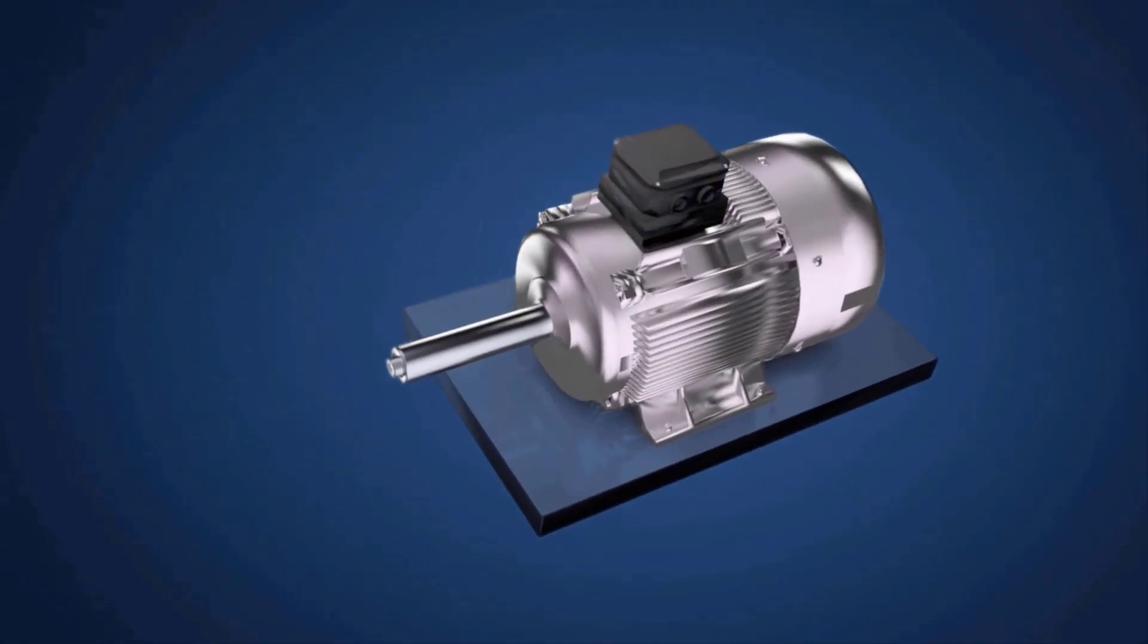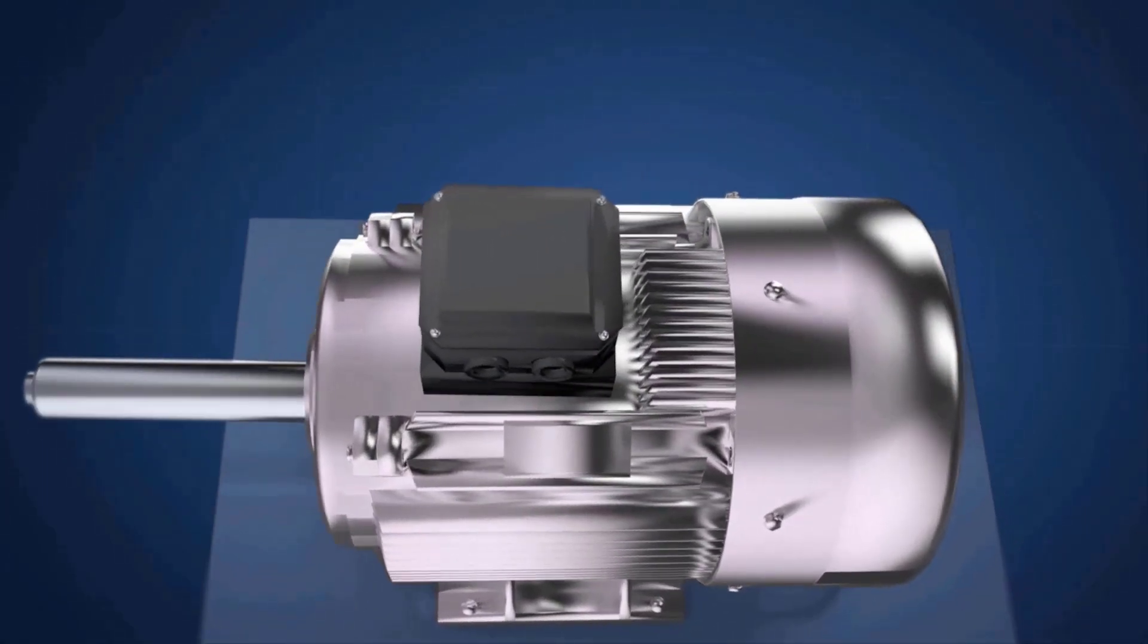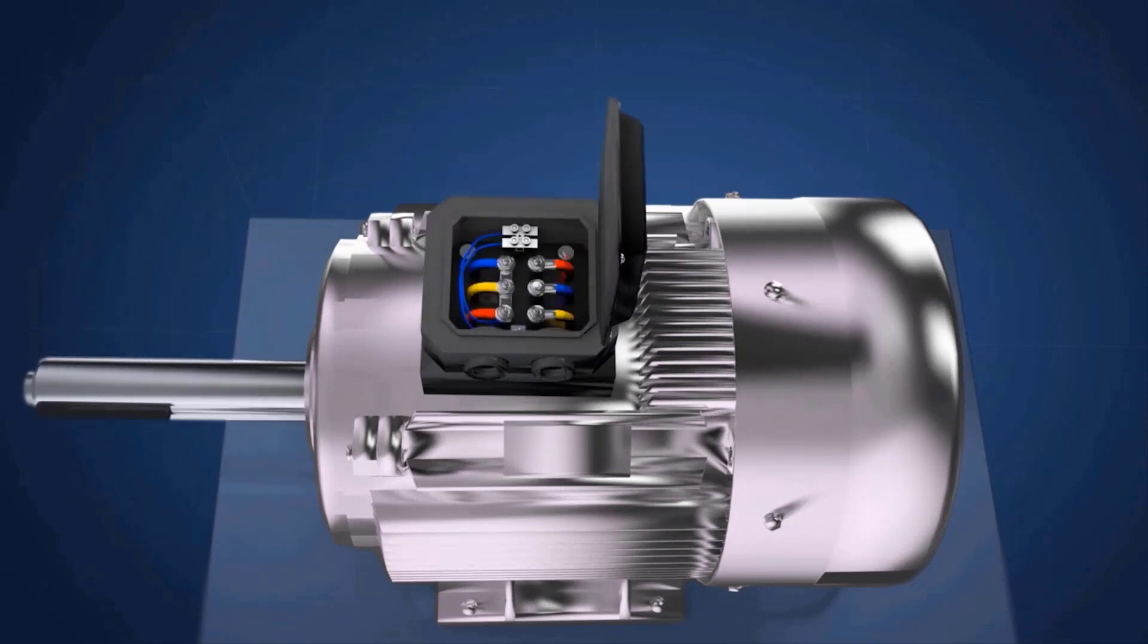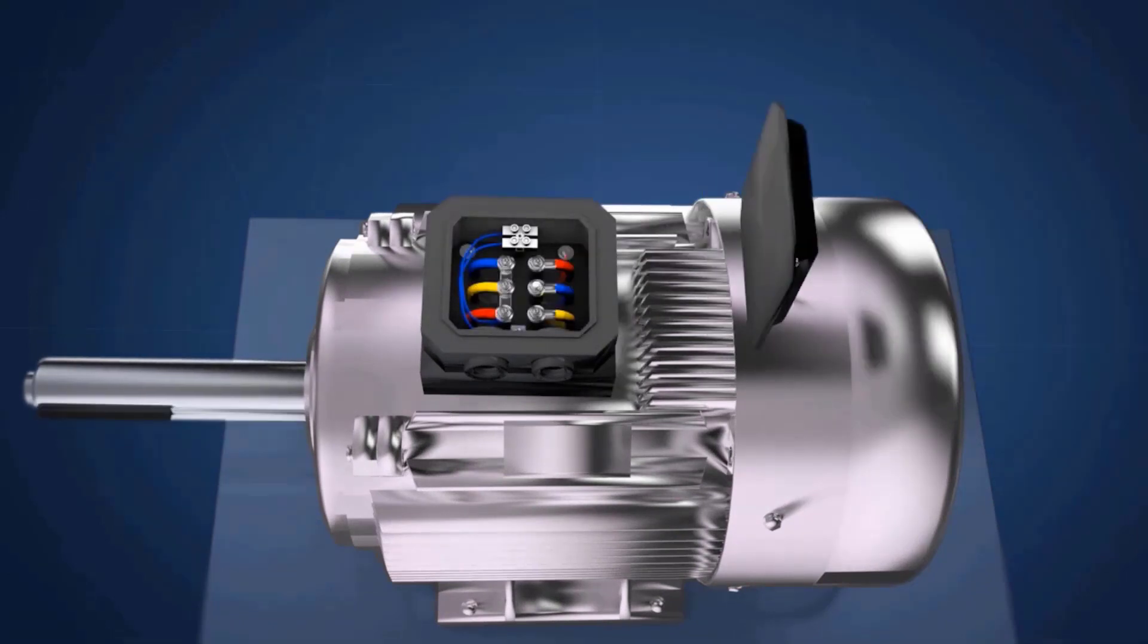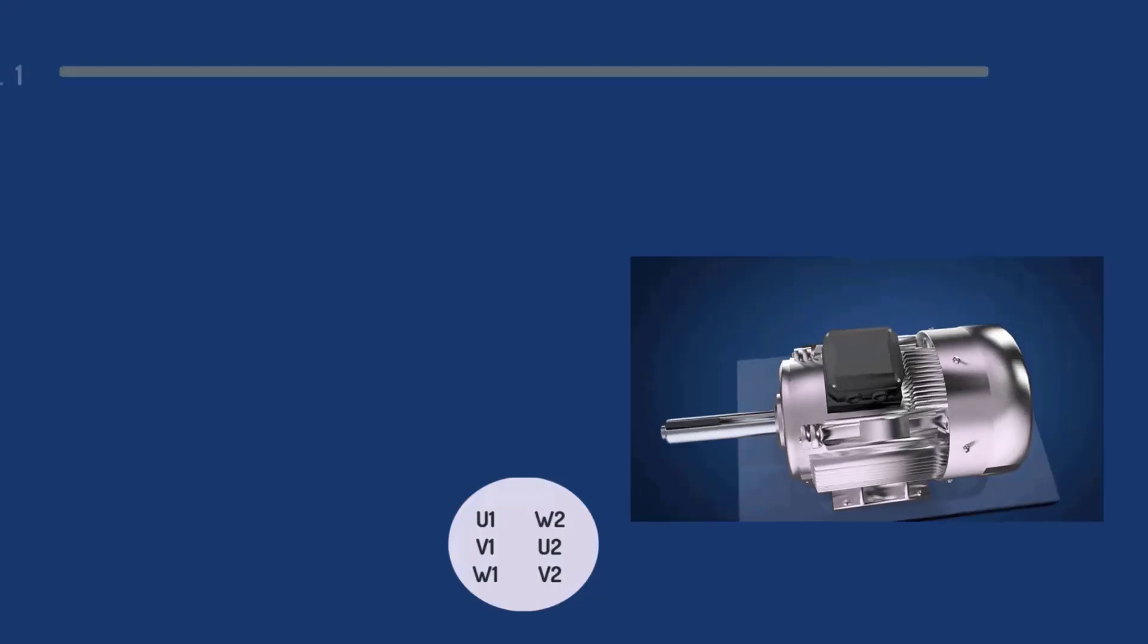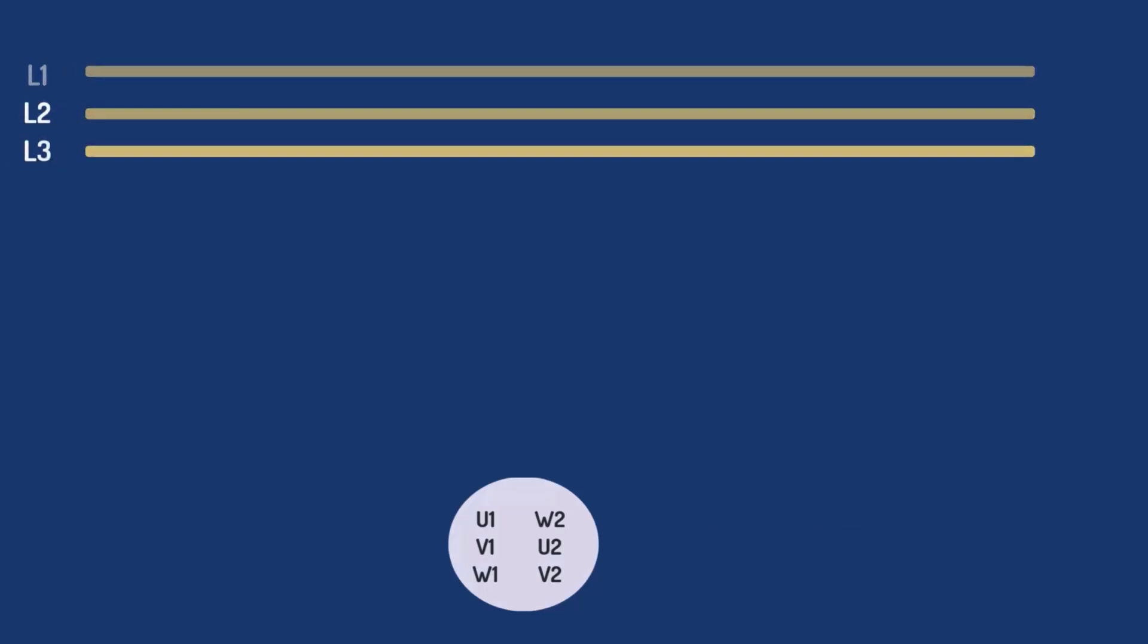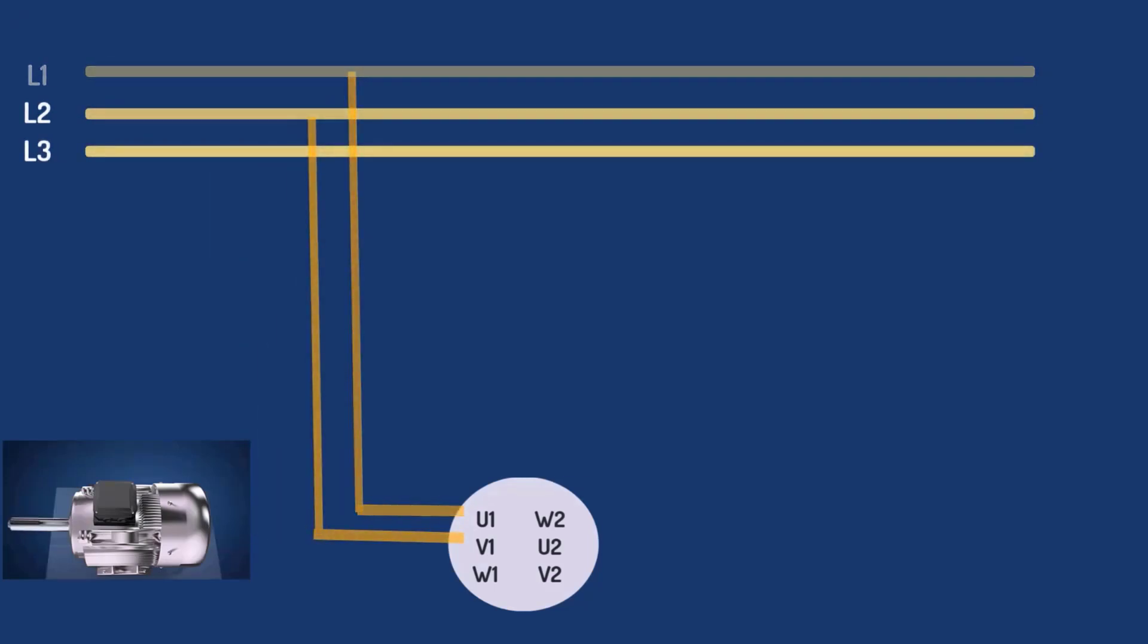It's important to see what's inside the terminal box of a motor. When we open the motor terminal box, you will see six terminals inside. To run the motor, we need to connect three-phase power supply to motor terminals: L1 will be connected to U1 terminal, L2 to V1 terminal, and L3 to W1 terminal.